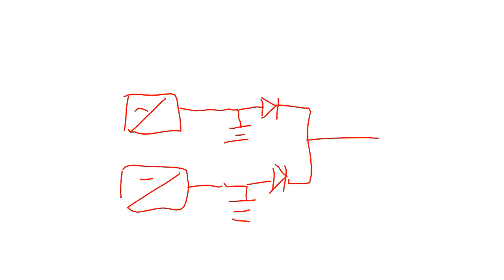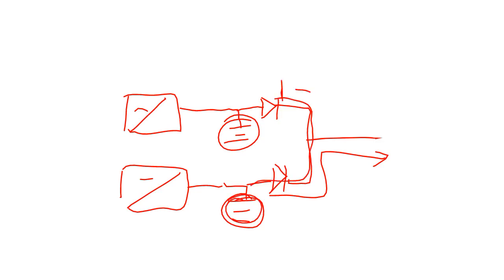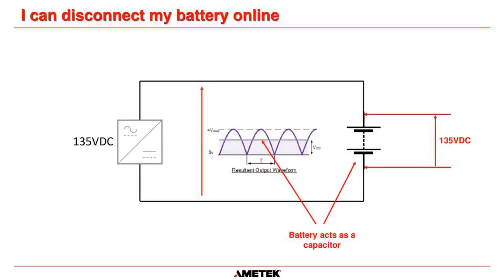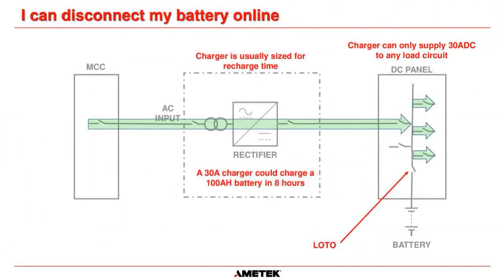And that way, this battery here can supply power out to the load circuits. But if there was a failure in this battery here and it had a short circuit or something in there, then this battery would not be affected because this blocking diode here, this cathode here, would not allow it to feed back into that battery. So you can use blocking diodes, and many people do. I'm just not a fan of them because it's an additional point of failure, in my opinion. But I'm not as passionate about that as many other things.